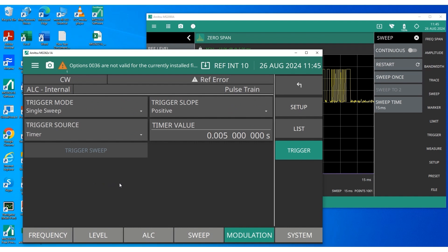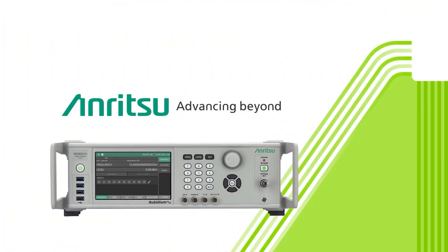Just to summarize: the timer source is used to insert a delay from the beginning of the pulse burst or pulse sweep to the beginning of the next pulse burst or pulse sweep. With five trigger modes discussed, Rubidium provides unprecedented flexibility in generating pulse patterns, both periodic and non-periodic. This flexibility is unique to Rubidium and is very useful for testing radar receivers.